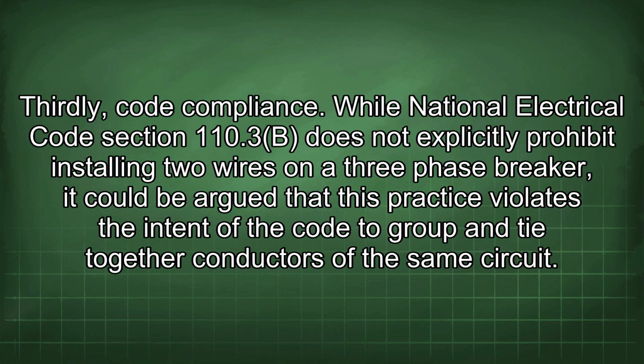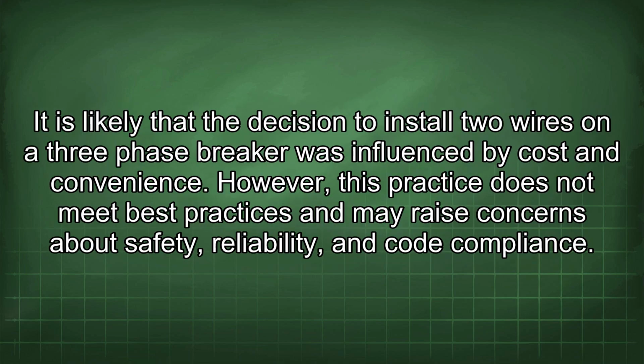Thirdly, code compliance. While NEC Section 110.3b does not explicitly prohibit installing two wires on a three-phase breaker, it could be argued that this practice violates the intent of the code to group and tie together conductors of the same circuit. It is likely that the decision to install two wires on a three-phase breaker was influenced by cost and convenience. However, this practice does not meet best practices and may raise concerns about safety, reliability, and code compliance.